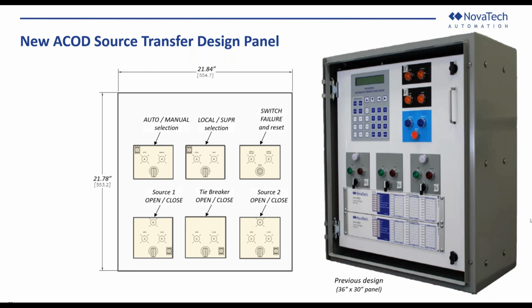The 3 bottom panels and the gray panels that you see there on the right are the same for both. These indicate the position and also allow for manual control of the switches that ACOD is connected to. The left is for source 1, the right's for source 2, and the bus tie control and indicator lights are in the middle. There's also extra lamps on those, the white lamps. Those indicate the potential for each source, because ACOD is hooked up to PTs and it's just monitoring voltage. The green and red lamps shown are indicating the position of the switches, open or closed. And as mentioned, if the ACOD is in manual mode and in local, then an operator is able to change the position of the switches and operate the switches with the controls there.